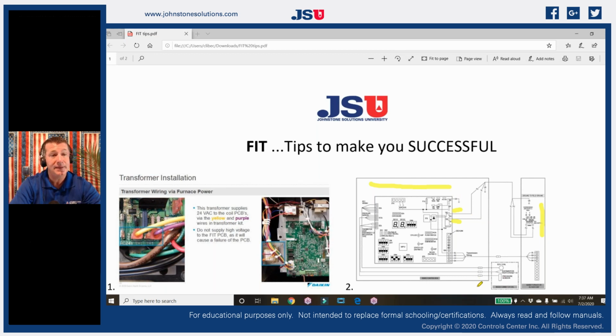And off from that control board, we're going to have some inputs. So this is the actual sensors that are on our coil. We're going to have our pressure. It says pressure sensor. It's a true transducer. We're going to have a couple temperature sensors, and then we're going to have the actual solenoid of the EEV. And then from the furnace or air handler, we're going to supply an additional signal, which is the actual operating signals. So for our Daikin, we're going to use blue and red to feed 24 volt AC over to the board, and we're going to use number 1 and number 2 for communicating. So all of our communicating signals are really just happening on number 1 and number 2. And we'll talk about that here in just a second, what we're actually doing with those. It's pretty simple technology.